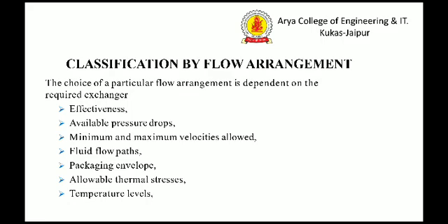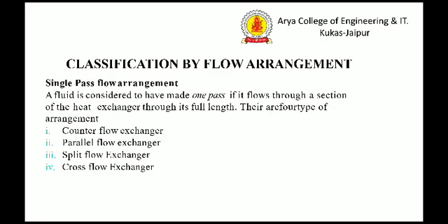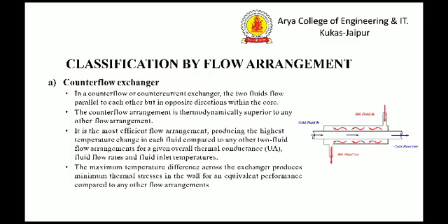So, the choice of a particular flow arrangement depends on the required exchanger effectiveness, available pressure drop, minimum and maximum velocity allowed, fluid flow path, packaging envelope, allowable thermal stresses and temperature level. Now single pass arrangement. A fluid is considered to have made one pass if it flows through a section of heat exchanger through its full length. There are four types of arrangement: counter flow, parallel flow, split flow and cross flow.